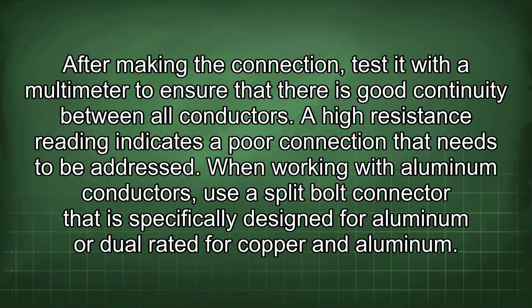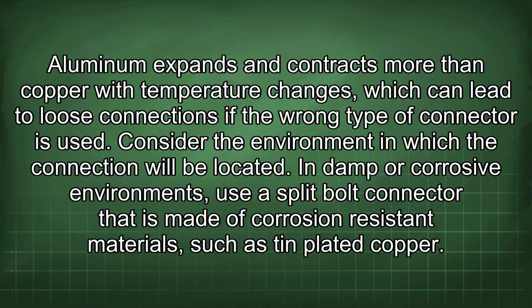When working with aluminum conductors, use a split bolt connector that is specifically designed for aluminum or dual-rated for copper and aluminum. Aluminum expands and contracts more than copper with temperature changes, which can lead to loose connections if the wrong type of connector is used. Consider the environment in which the connection will be located. In damp or corrosive environments, use a split bolt connector that is made of corrosion-resistant materials, such as tin-plated copper.